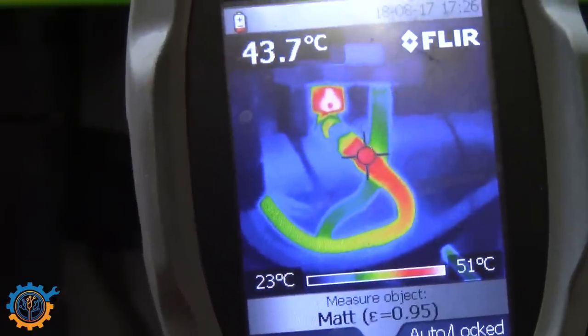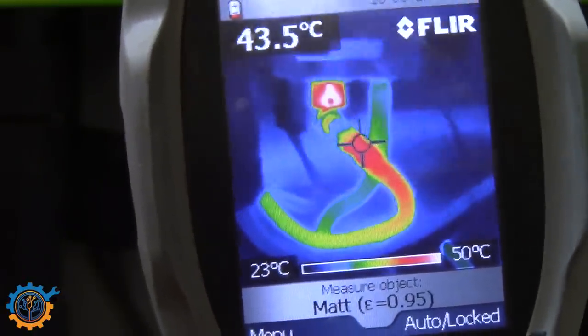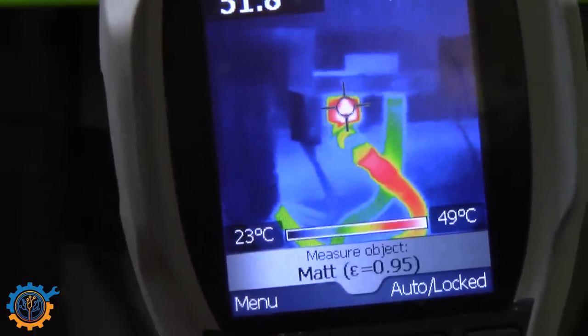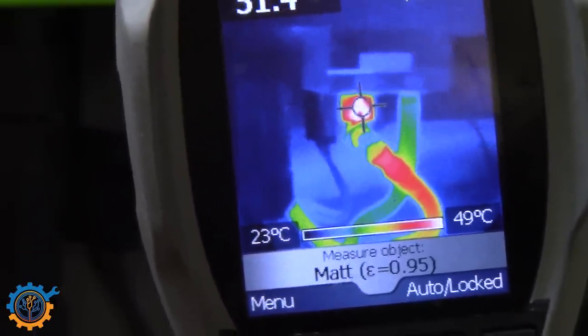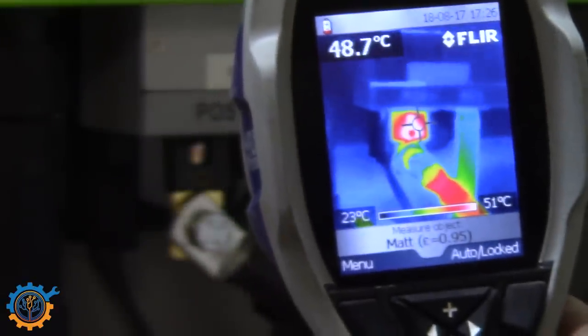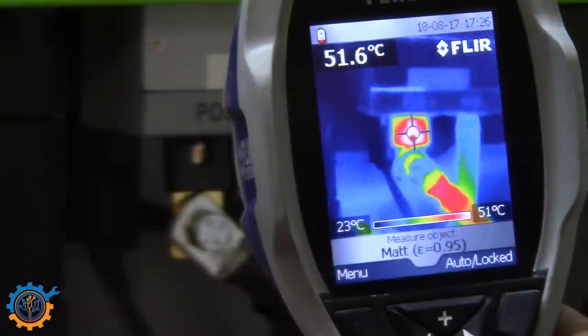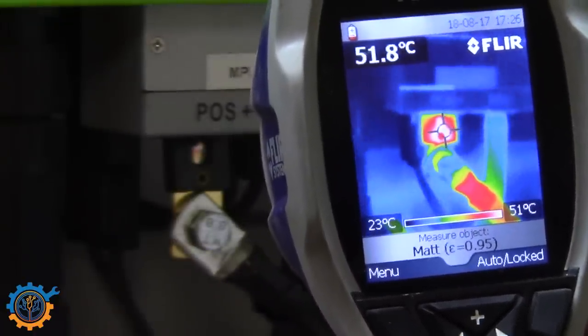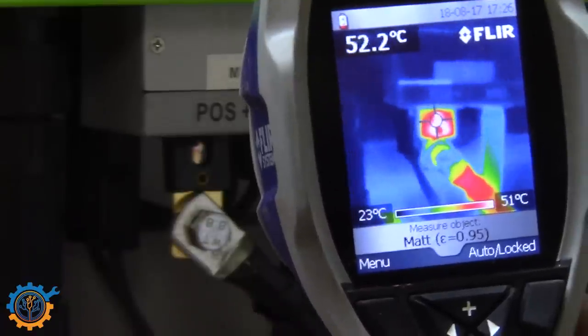Close to the connection we have around 43 to 44 degrees, and the fuse itself is way above 50 degrees. We are only pushing around 40 to 100 amps, so we are talking about five kilowatts out of this.